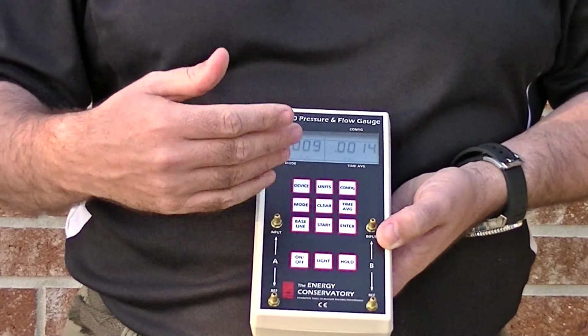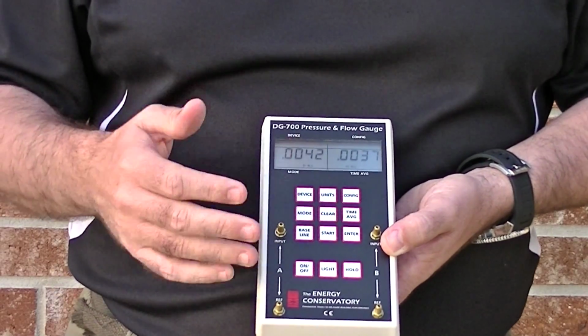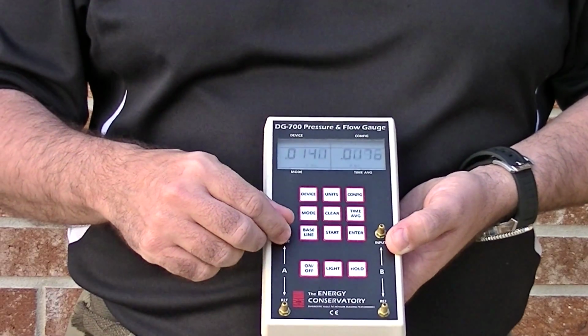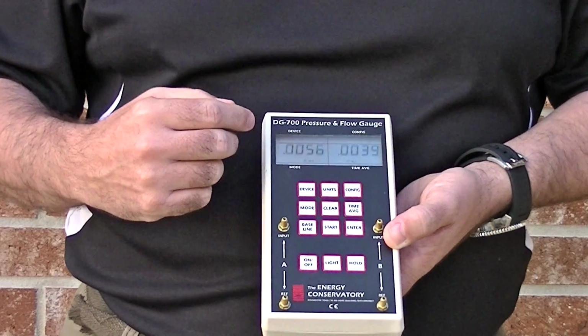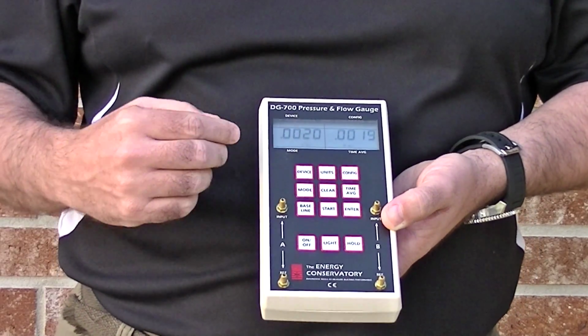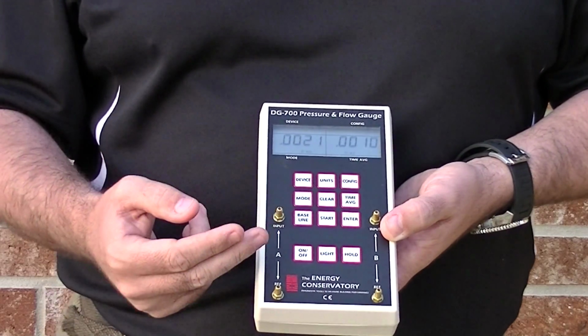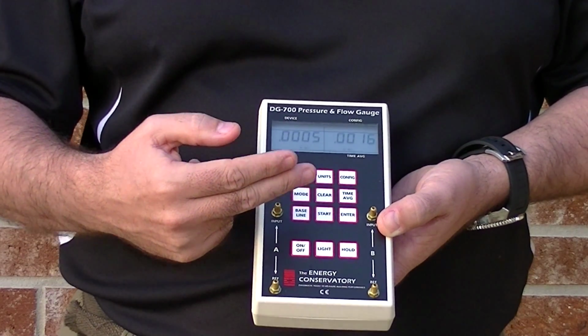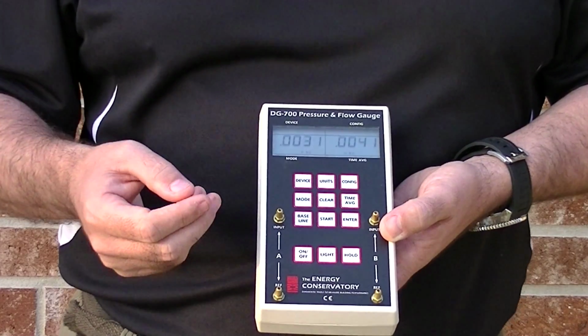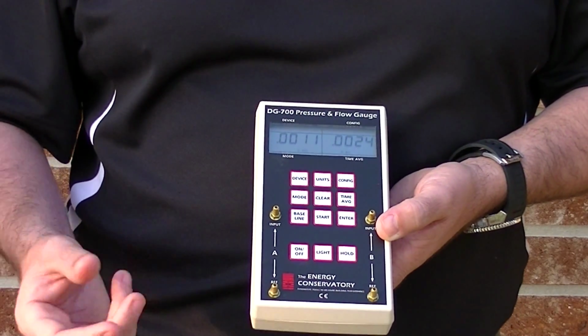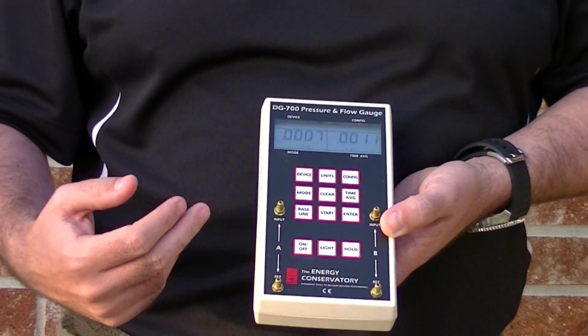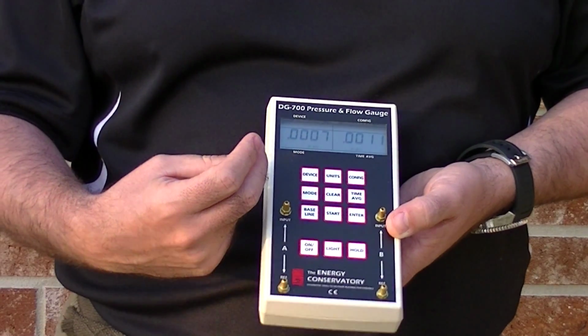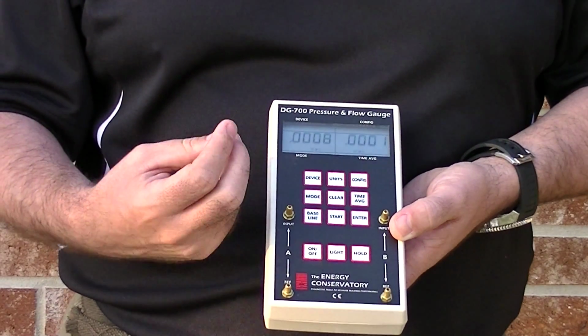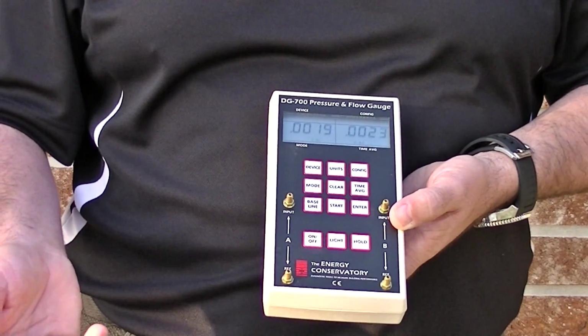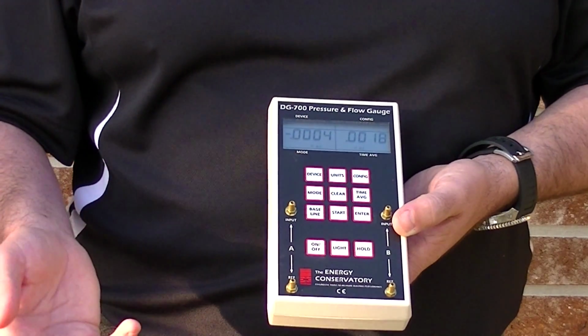You can see we're out here, it's a little bit windy, and it's bouncing all over the place. When we connect our pressure probes up there, the side that's connected to the return side of the air handler is going to read a negative number. The side that's connected to the supply side of the air handler on the supply plenum is going to read a positive number. To take a total external static pressure, you just ignore the positive and negative signs and just add those two values together. That will give you your total external static pressure that you can then look up on a blower table to confirm what the airflow is for the manufacturer's specifications.